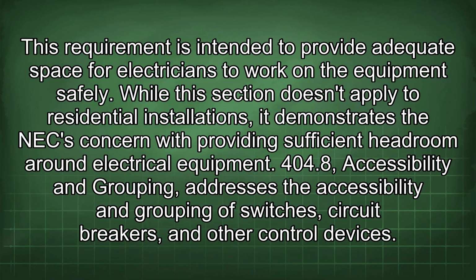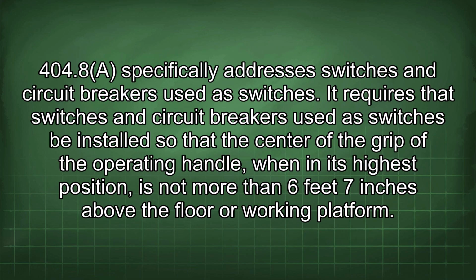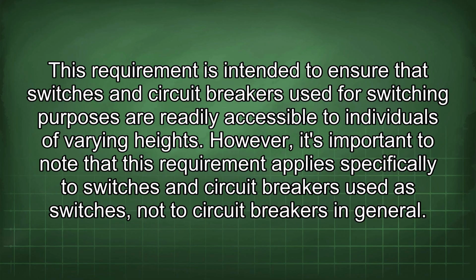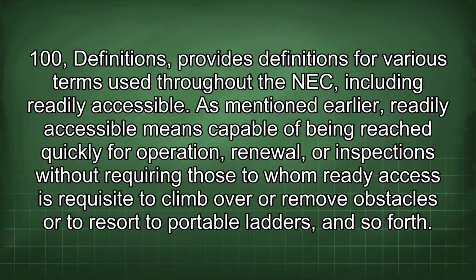404.8 Accessibility and grouping addresses the accessibility and grouping of switches, circuit breakers, and other control devices. 404.8 specifically addresses switches and circuit breakers used as switches. It requires that they be installed so that the center of the grip of the operating handle, when in its highest position, is not more than 6 feet 7 inches above the floor or working platform. This requirement is intended to ensure that switches and circuit breakers used for switching purposes are readily accessible to individuals of varying heights. However, it's important to note that this requirement applies specifically to switches and circuit breakers used as switches, not to circuit breakers in general.